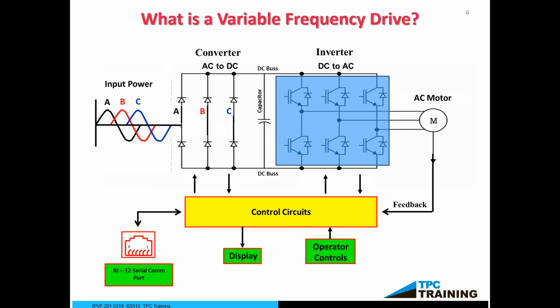So if you're qualified to look at your units and operate the display of your units at half speed, you're going to note on your display it's going to be half voltage. So say, for example, if I have a 480 volt system and I'm running at half speed, you'll note that it's going to be reading 30 hertz and 240 volts. Or if you're at a quarter speed, you're going to be looking at 15 hertz and 120 volts. So it's not just a variable frequency drive, it's a variable voltage and frequency drive. And that's based on what they call the volts to hertz ratio.